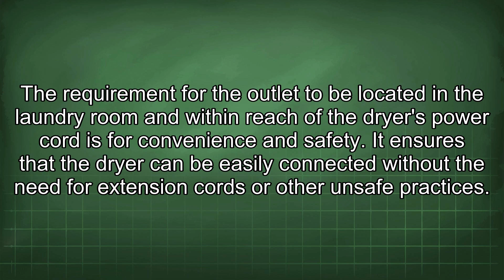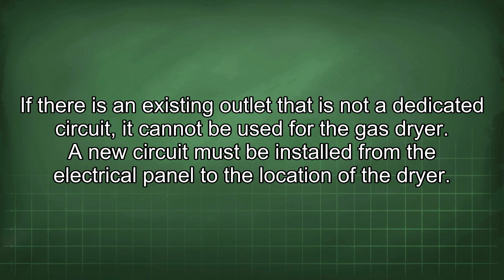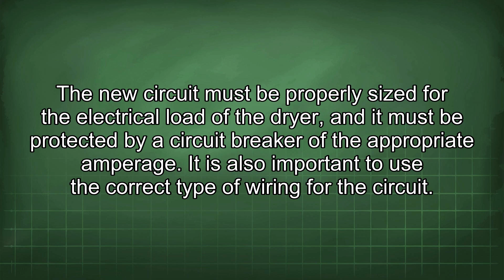If there is an existing outlet that is not a dedicated circuit, it cannot be used for the gas dryer. A new circuit must be installed from the electrical panel to the location of the dryer. The new circuit must be properly sized for the electrical load of the dryer, and it must be protected by a circuit breaker of the appropriate amperage. It is also important to use the correct type of wiring for the circuit. The wiring must be rated for the amperage of the circuit and must be installed in accordance with the NEC.